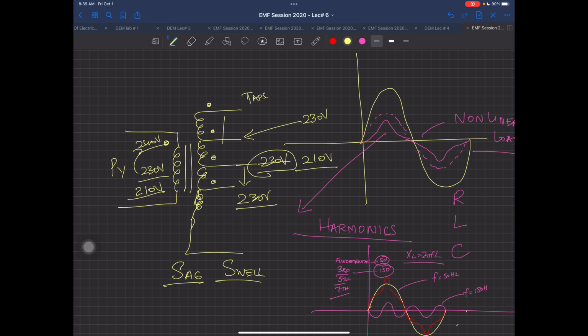Your fridge is filled with freon gas, and that gas is under pressure inside the chamber and the compressor. The compressor has a constant load on it. So it has to pressurize that gas and send it back to the chamber so it can liquify and cool again. If your WAPDA voltage goes down below 230 volts to maybe 190 volts for example...